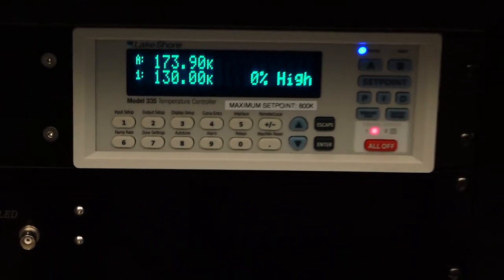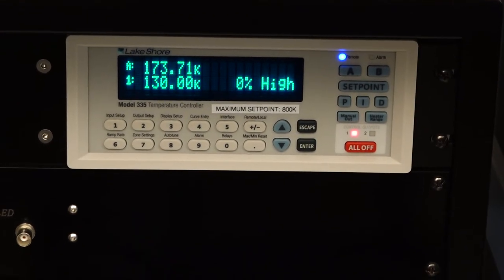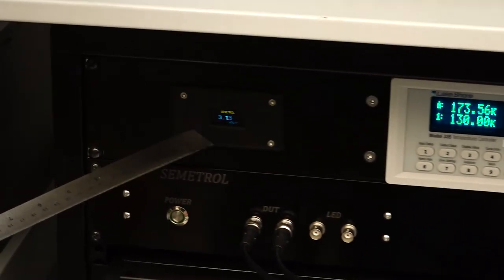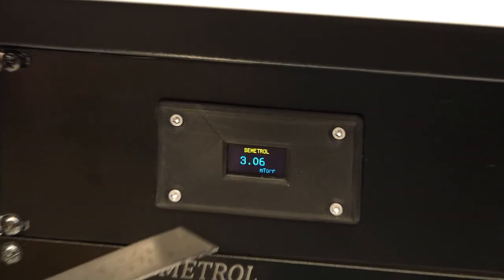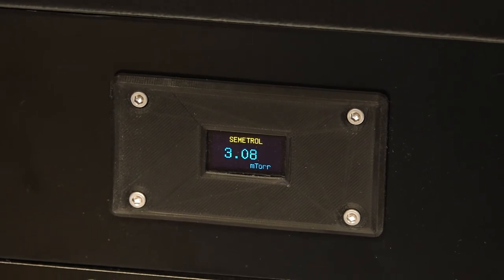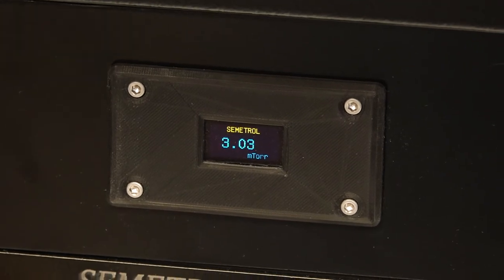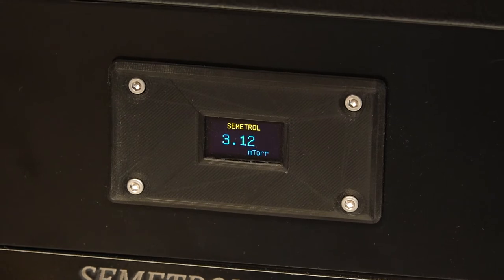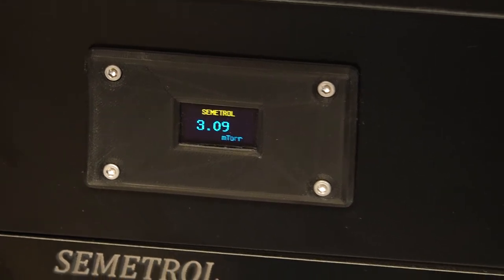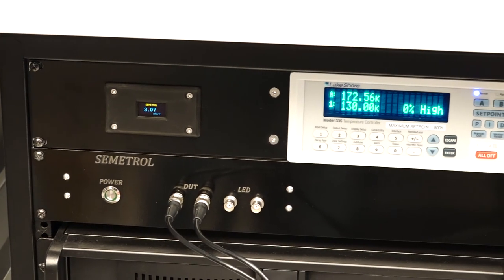One more thing to notice is that the chamber pressure is well below 10 millitorrs, it is around 3 millitorrs. One has to ensure that the chamber pressure before the cooling process starts is below 10 millitorrs. The cooling process or the DLTS measurements must not be initiated if the chamber pressure is higher.